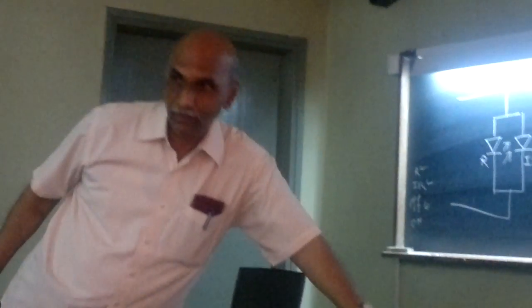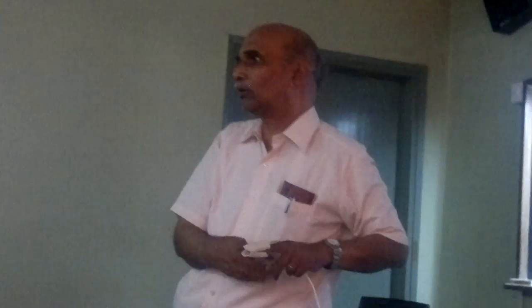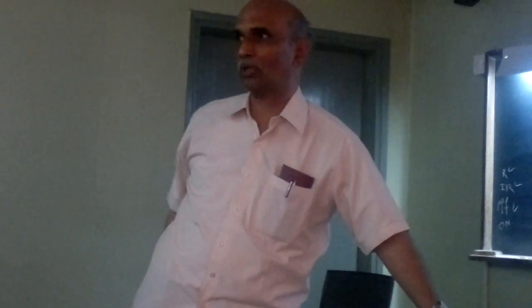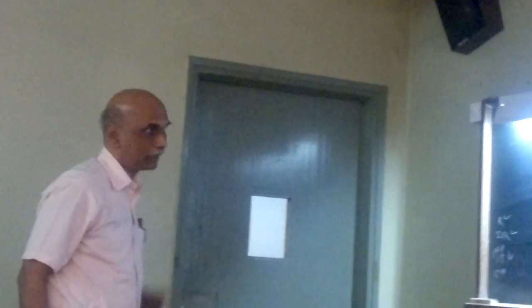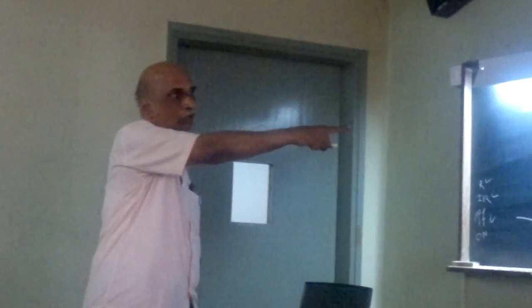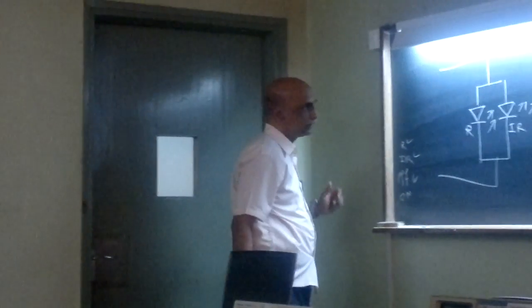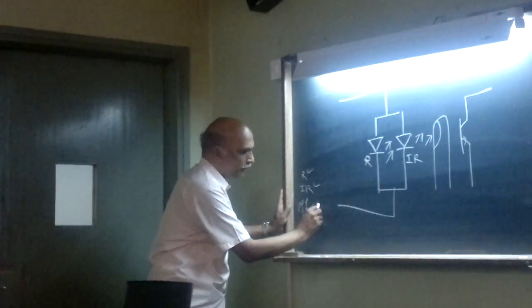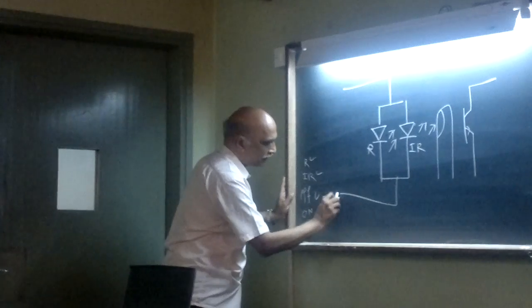Why is it ambient light? Because if you open this and put your finger inside, there is no way you can avoid the ambient light from going to the detector, however you try. You can put it inside an envelope and ensure that ambient can be minimized, but we can't even do that. So this detector has one output which is called the ambient output. When it's off, you are looking at the ambient light.